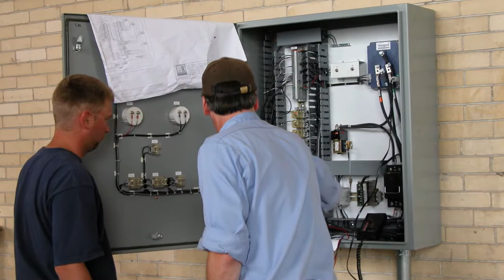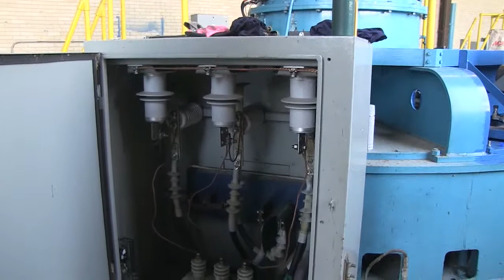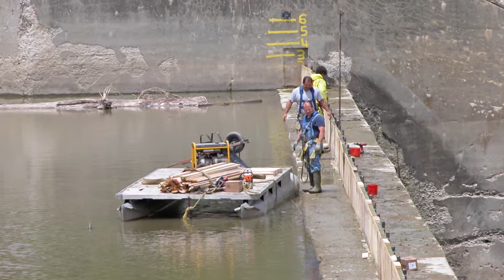To reduce the risk of further damage due to lightning, BMU had the hydro plant and related equipment tested for adequate grounding and installed lightning arresters for all units in operation. In the spring of 2002, BMU crews installed flashboards on the crest of the dam, and the additional pool of water was used to improve generation. For the year, the Auglaize plant generated nearly 5.4 million kilowatt hours, which was better than expected, with dry weather and only 2 or 3 units available for generation during the majority of the year.